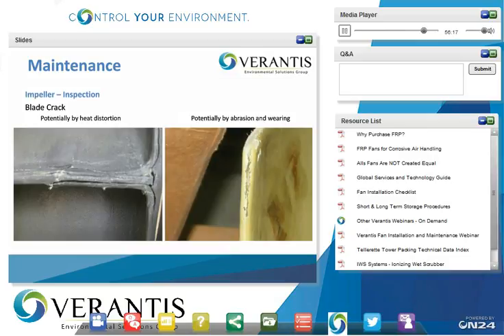Again, your inspections, the one on the left is one that was caused by heat. As well as the bowing, you're going to see it start tearing at the corners. The one on the right is abrasion and wear. Could potentially be water droplets, water going through the system to wear the protective coating off, or particulate. And again, it exposes glass fibers and makes it subject to chemical attack.